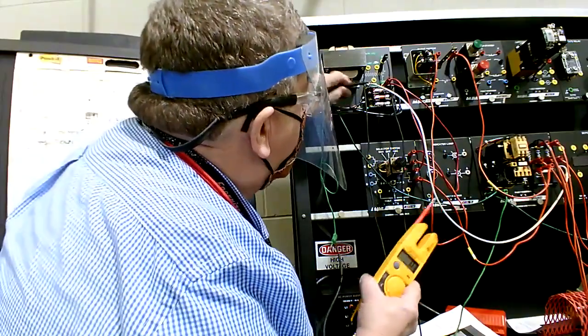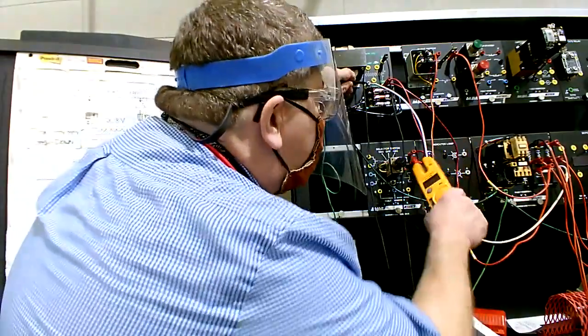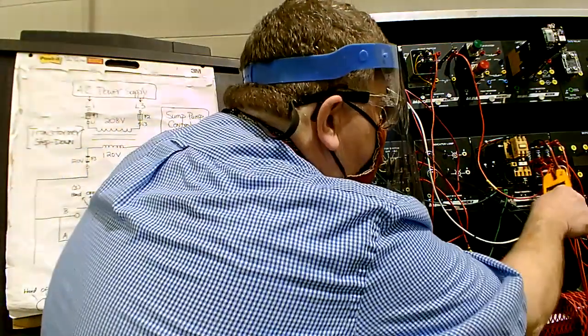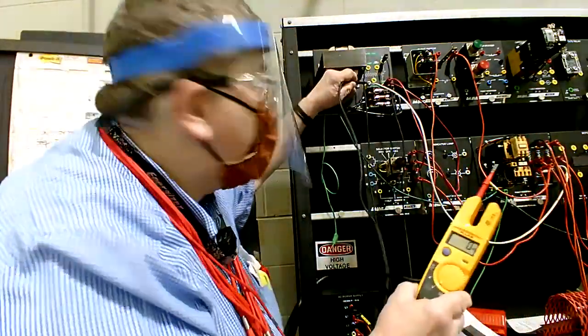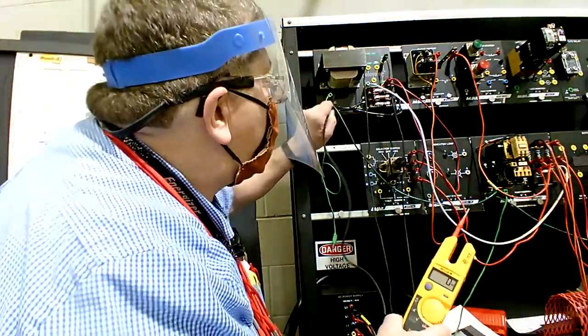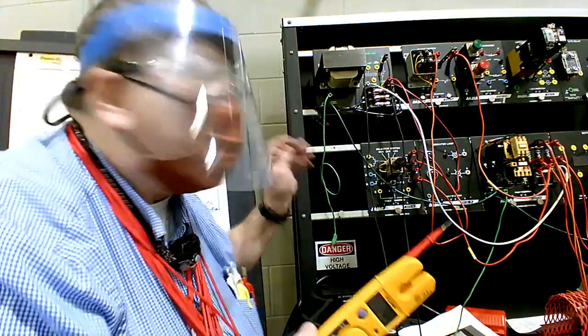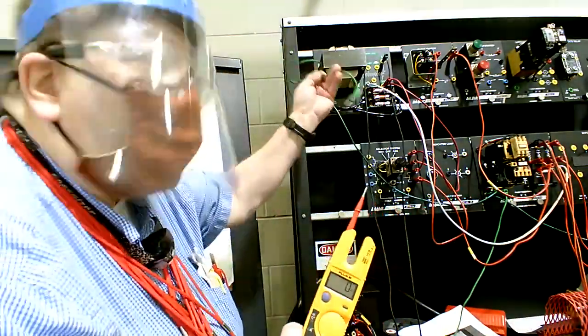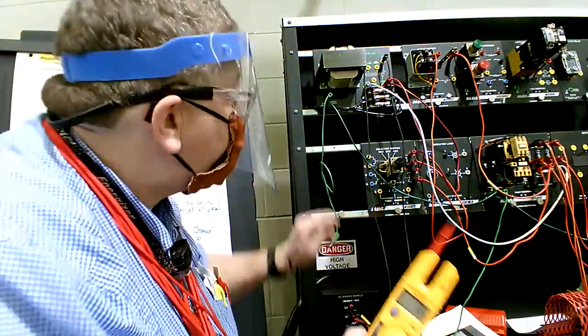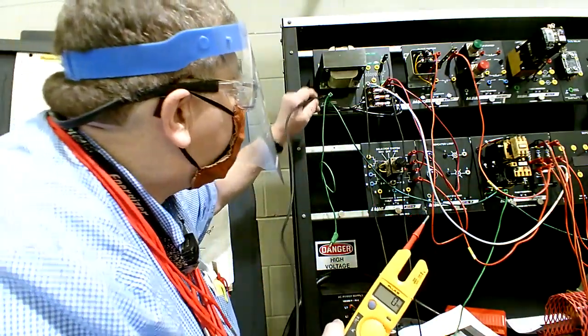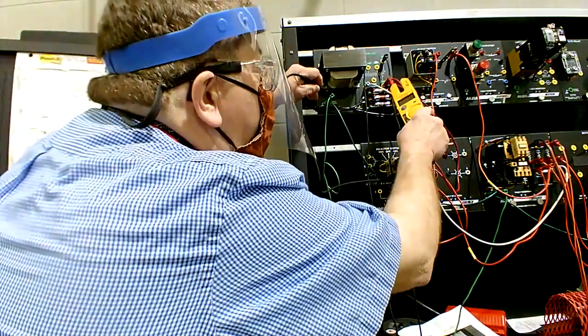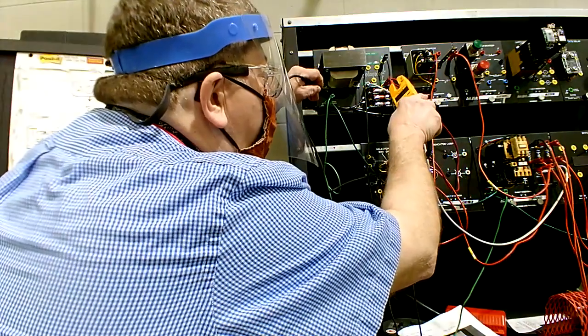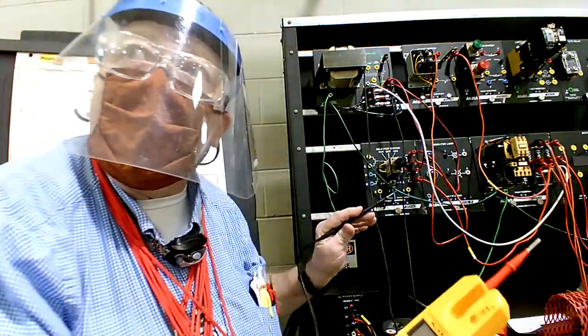You got to go to neutral here, and then test your signals going through the system, and then the meter will read correctly. Now, with neutral and ground not hooked together, like here, they're not hooked together. When they're not hooked together, watch this. If I go to ground and I go to here, you're going to get a bad reading. It's not going to say 120. It's going to be some way off number.